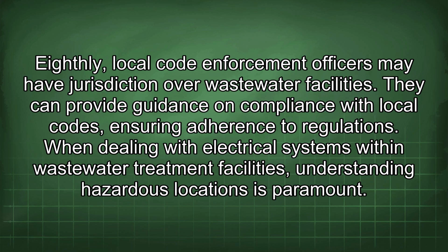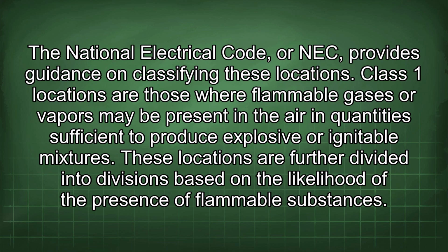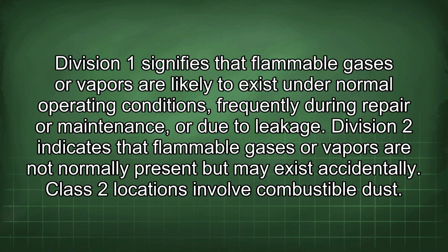When dealing with electrical systems within wastewater treatment facilities, understanding hazardous locations is paramount. The National Electrical Code, or NEC, provides guidance on classifying these locations. Class 1 locations are those where flammable gases or vapors may be present in the air in quantities sufficient to produce explosive or ignitable mixtures. These locations are further divided into divisions based on the likelihood of the presence of flammable substances. Division 1 signifies that flammable gases or vapors are likely to exist under normal operating conditions, frequently during repair or maintenance, or due to leakage. Division 2 indicates that flammable gases or vapors are not normally present but may exist accidentally.